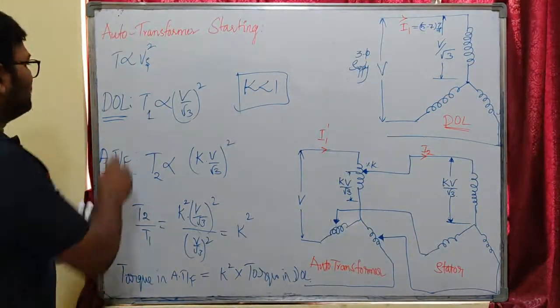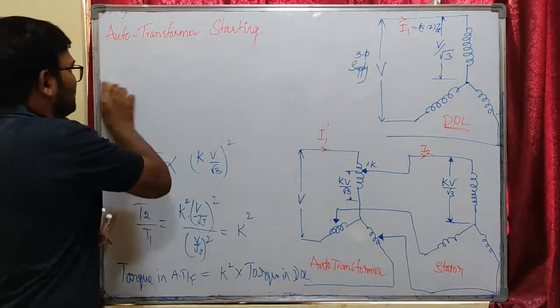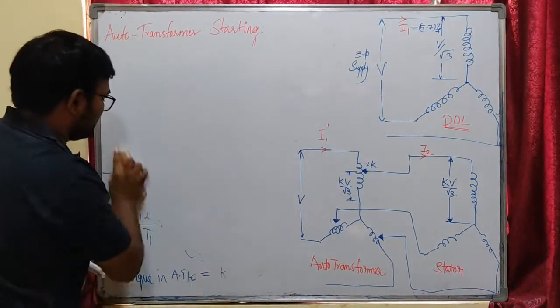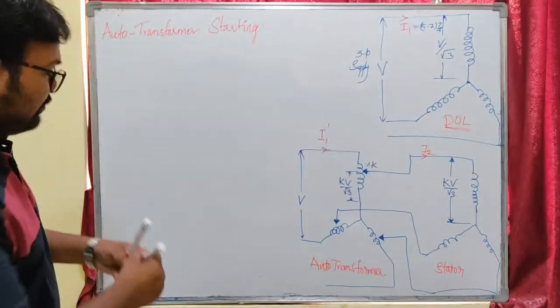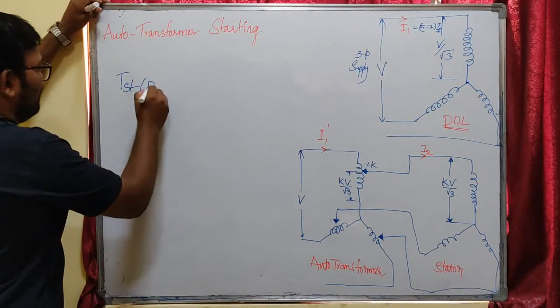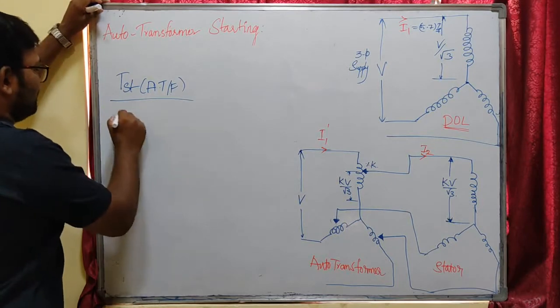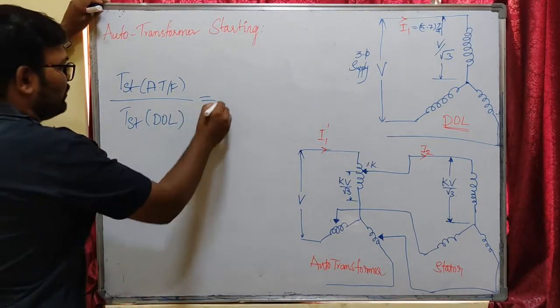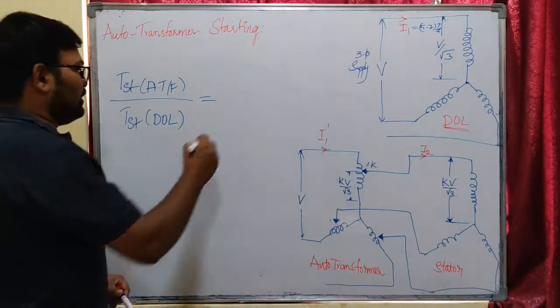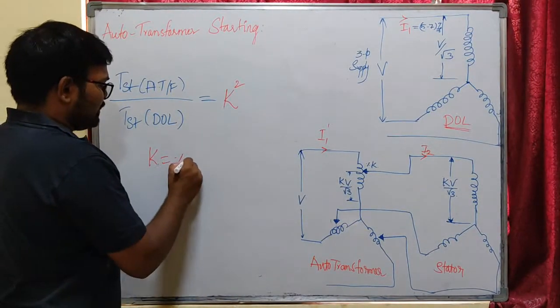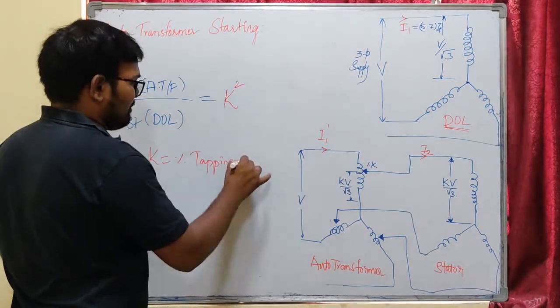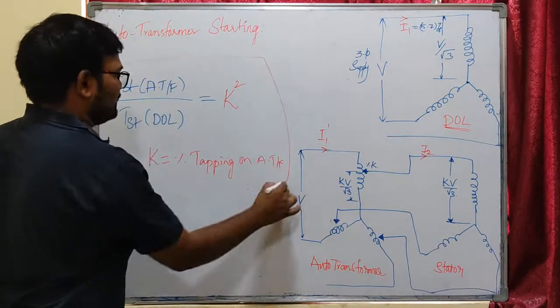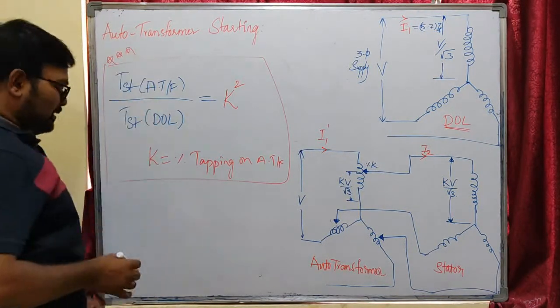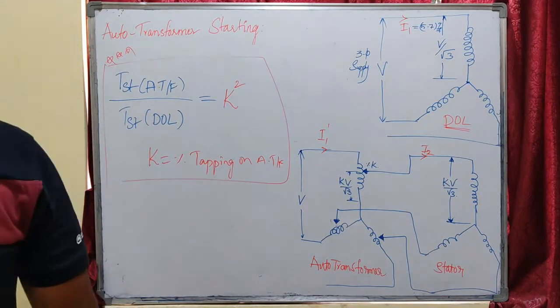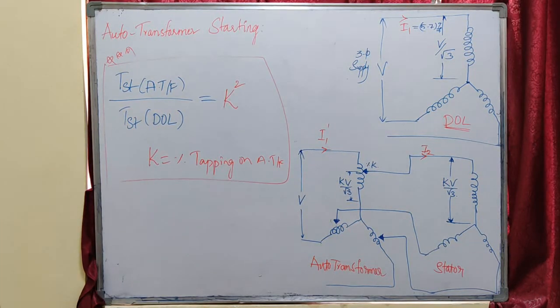So I am going to see how the starting torque is reducing in the auto transformer starting. Here the starting torque of auto transformer by starting torque of DOL equals, what is the value? K square, where K is the percentage tapping on the auto transformer. This is a very important relation: the starting torque of auto transformer, compared to the starting torque of direct online starting, is equal to the percentage tapping whole square.